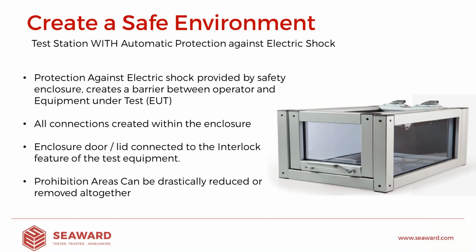So let's first start talking about a test station with automatic protection. As I said previously, a test station with automatic protection against direct contact simply stops anyone from coming into contact with the item under test during the time that the test is being performed. Now, traditionally, this is performed by dropping the item into an enclosure, as you can see on screen. We open a lid, we put the product inside, we make all of the relevant test connections in order to perform the test. We close the lid, we start the test away, and anything that could go wrong is going to happen inside a nice insulated box, keeping us nice and safe from harm. This is probably the ultimate safe way of performing testing.